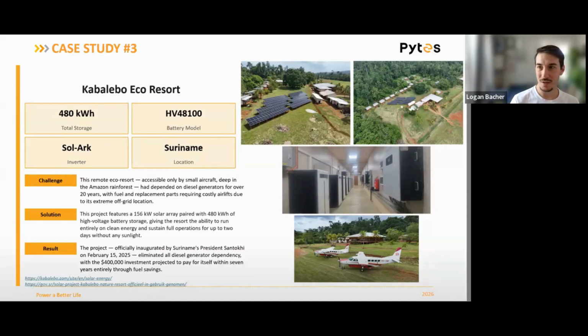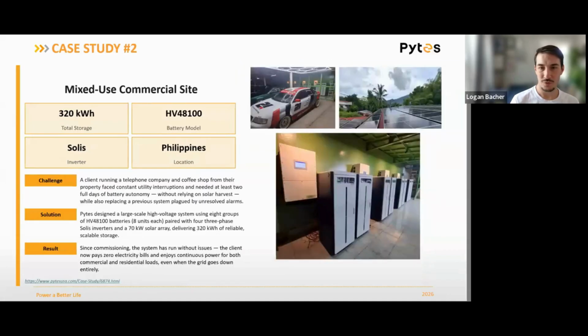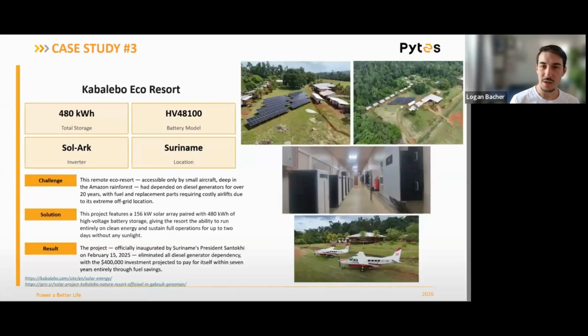Let's go back to this one. So again, this is following that 2-to-1 architecture that I keep reiterating. The batteries are independent here. So if one shuts down or has a problem, typically the other group is still operating independently because they're going to separate inputs on the inverter. In a system like this, though, it's honestly really hard to see in the picture there, but I think this system had 3 battery cabinets per every inverter. So now we've exceeded that 2-to-1.